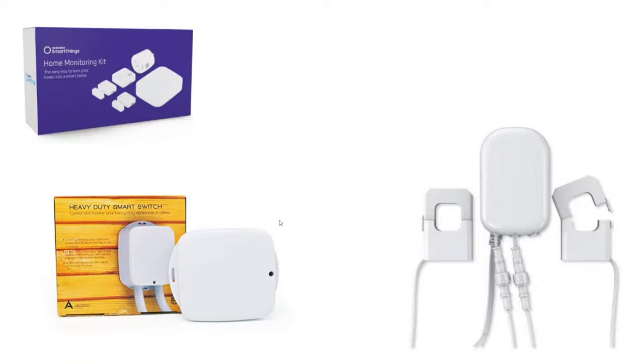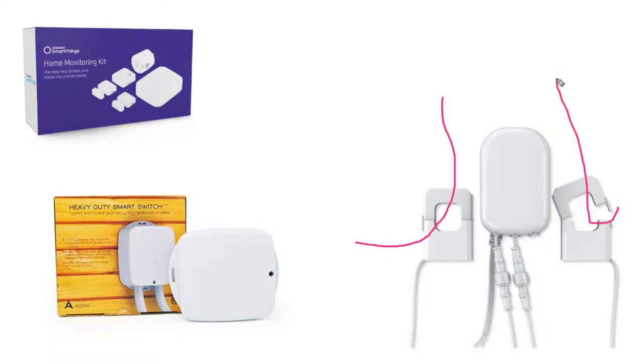In our smart home load control class, we talk about how you can monitor home power by putting your own energy meter in front of the meter, clamping around the main power lines that come into the house. Any intelligent grid-tied battery inverter, you're going to have to do the same thing. If you're buying a battery inverter and your intent is to produce a zero outflow system where you're not selling back to the grid, and you're not buying a whole house inverter, just something that can back up the whole house, you have to communicate between the battery inverter and the meter. Otherwise, the battery inverter can only control what's on its critical side, not what's on the other side of it.